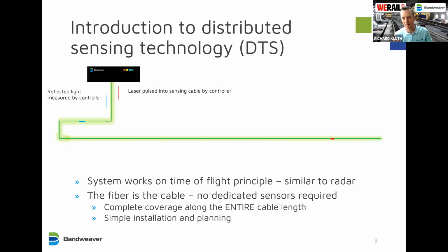That's why these systems are so clever, because it's really taking the noise out of the signal to noise ratio, getting rid of that and getting these tiny amounts back. But you're measuring this background. So if you had a break at this point here, your pulse would still be going to there. So you're not waiting for the pulse to get to the end to measure. It's as it's traveling, the light flows. So the electronics in the box are sampling super quickly, hundreds of kilohertz, in order to get that. So as soon as the pulse is on there, it's faster than we can comprehend as humans.